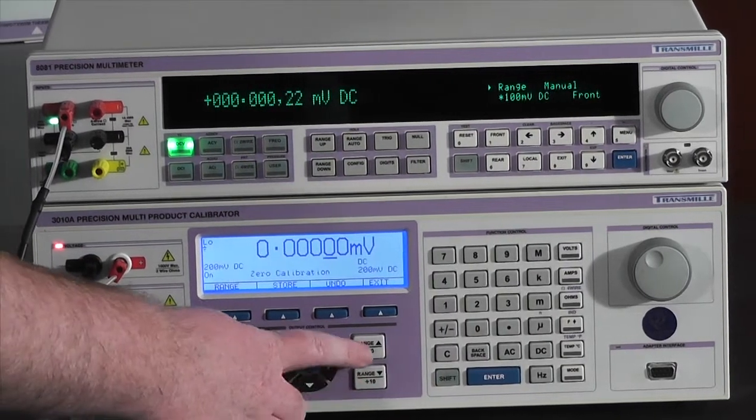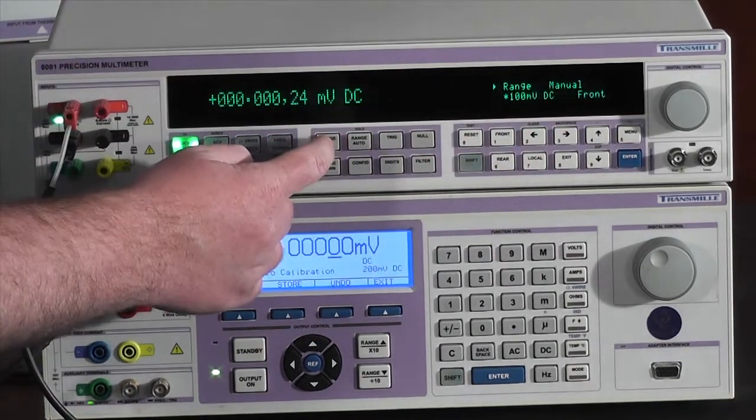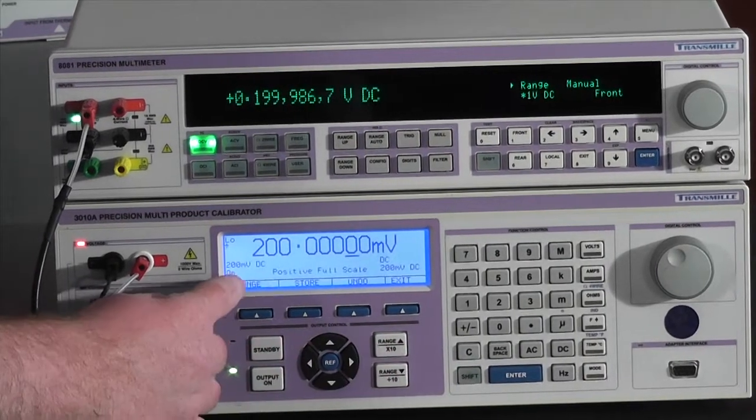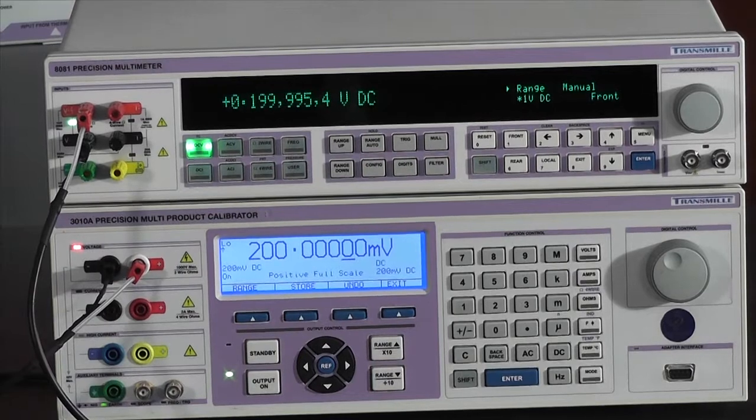I am now going to press range up to go to the next calibration point. At this point, I'm also going to change the range on my multimeter. So pressing range up has now gone to the positive full scale adjustment point.